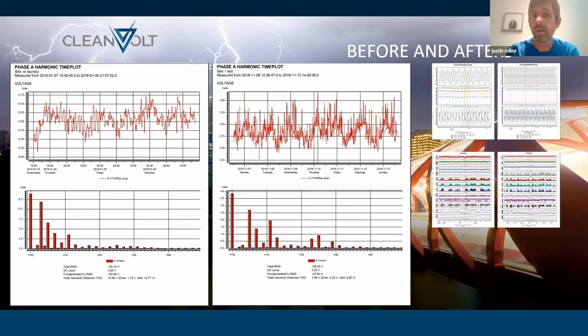And of course, you can still see there's some order of harmonics. I think that's the fifth order of harmonic, just around 2.5. The 7th order and the 11th order are the three most prominent orders in this after test. But there's equipment within this facility that are generating those harmonics. And if, say, these levels were above 519 standards, then you would probably need a harmonic filter to address those.